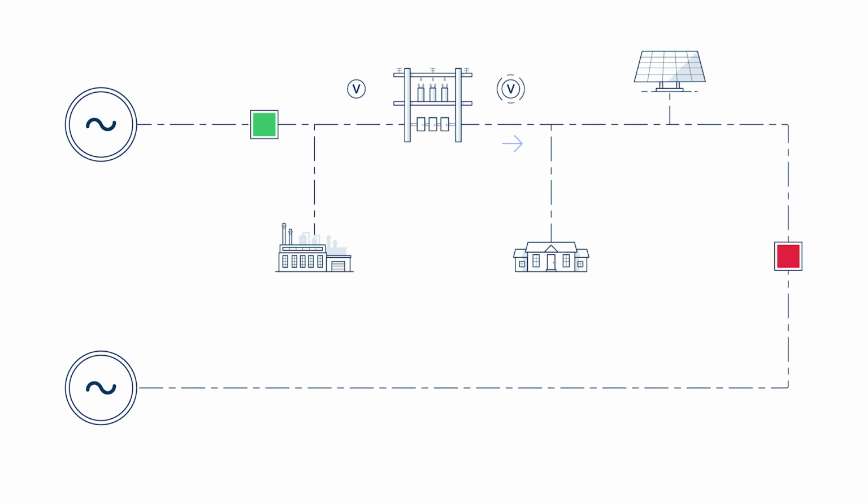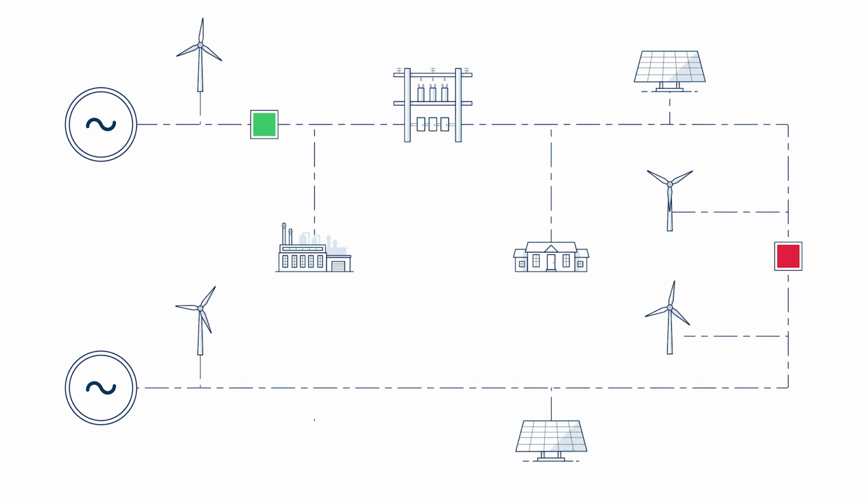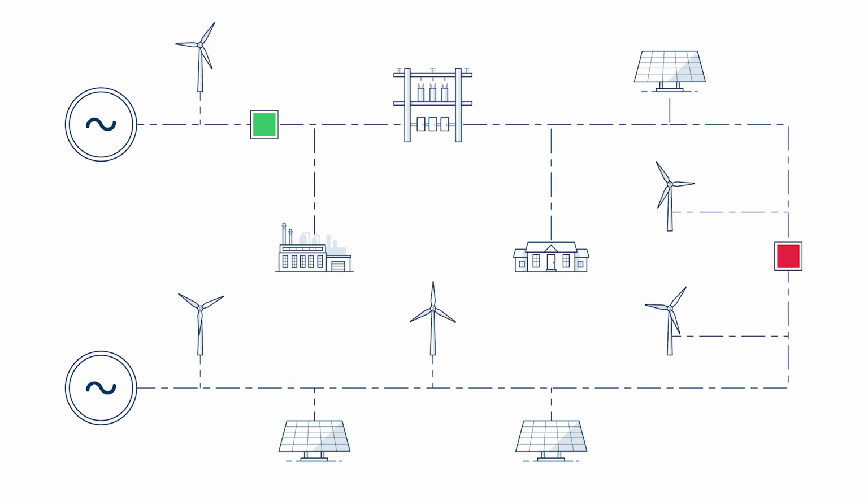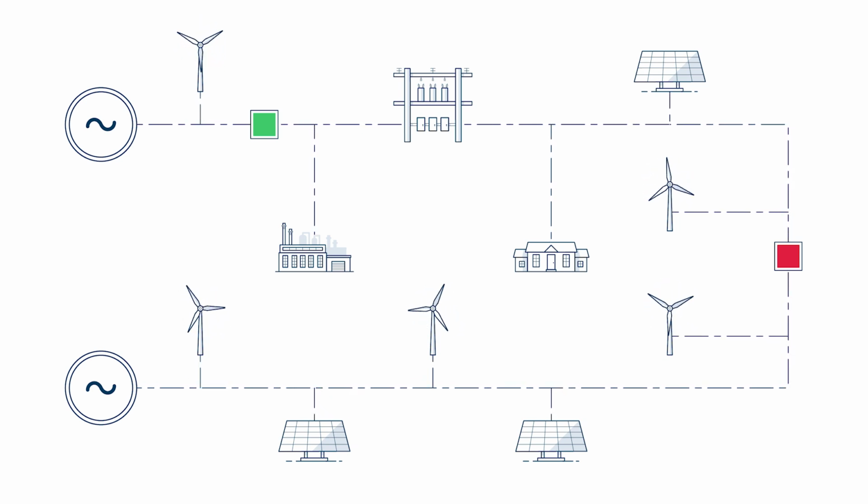But this time, Flex DG measurements show that the voltage regulator is having no effect. The power on that side must be coming from a stiff source. The control now switches direction, tapping the regulator to control the voltage in the proper direction, downstream from the stiff source. Using this method to detect stiff sources, Flex DG in the SEL 2431 can always find the correct direction to regulate voltage. And it's future-proof. No matter how many DERs are added in your system or where they're located, it still works.